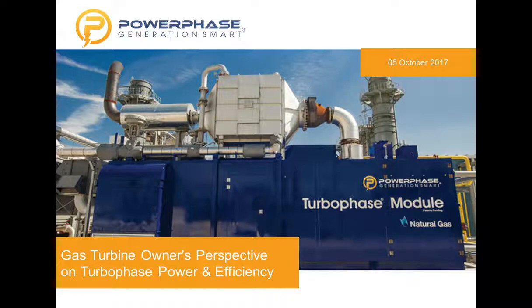Okay, great. We're staying with you, Steve, this next question, which is asking what modifications to the turbine or turbines are required to accept the compressed air from the Turbophase system? Sure. Well, nice about our OEM friends, there are connection points on every gas turbine that are either not used at high part load or base load applications, or are just simply blanked off for other purposes. So whether you're going from like an LM6000, where there's literally a port that's used for the cabin bleed air on an aircraft, right? Because it's a flight engine, which is not used on the ground, we tie into that port. On a GE frame machine, there are inlet bleed heat systems in the compressor discharge casing that we can tie into. On the Mitsubishi, Siemens, I should say Westinghouse frames, there are turbine air coolers, rotor air coolers that we can tie into. Obviously on the Alstom 13E2s, GT24 and 26s, there are IBH systems we can tie into as well.